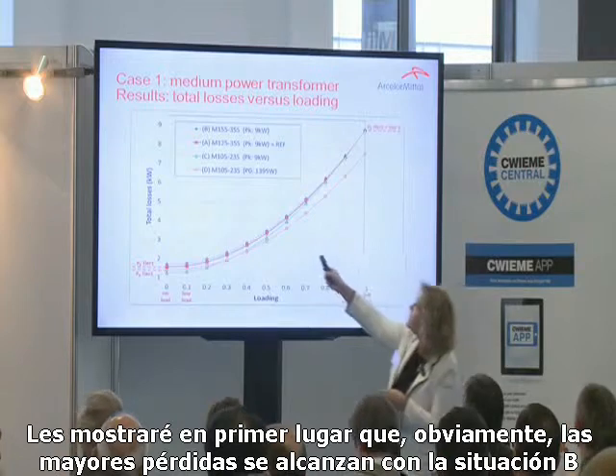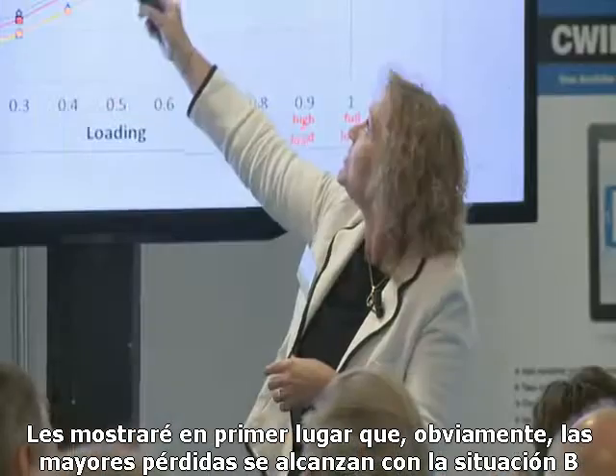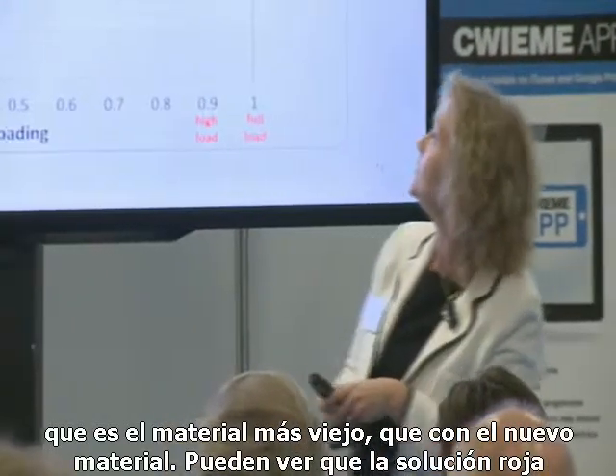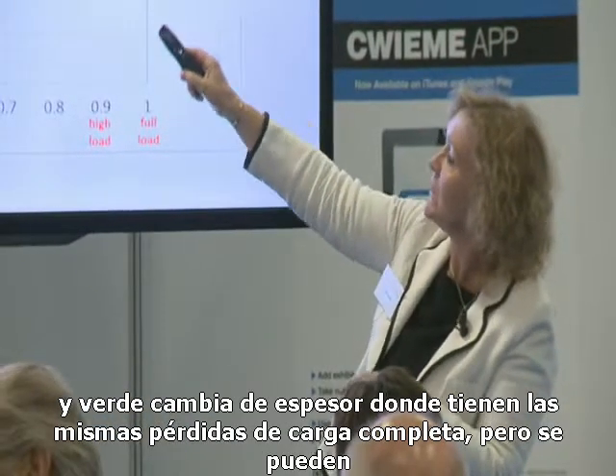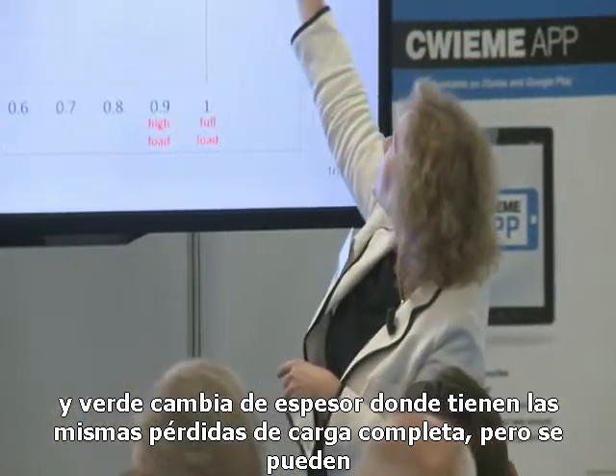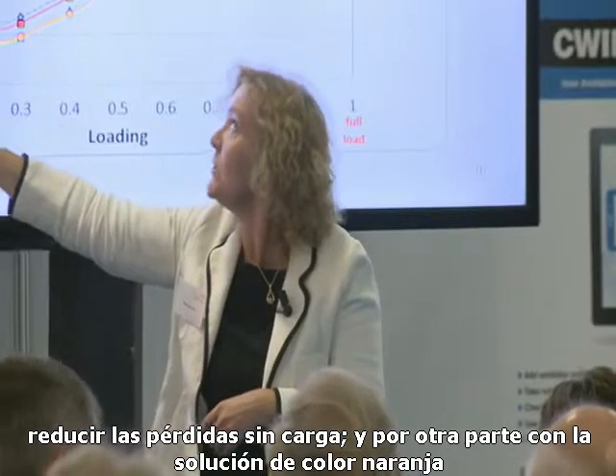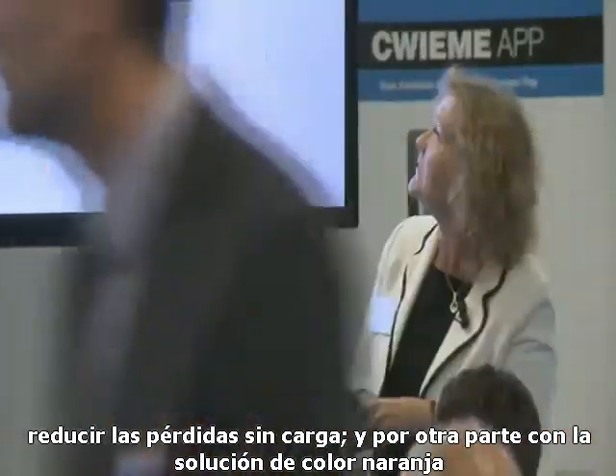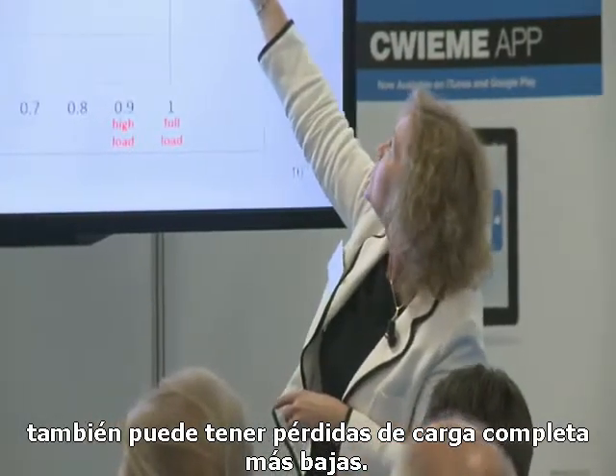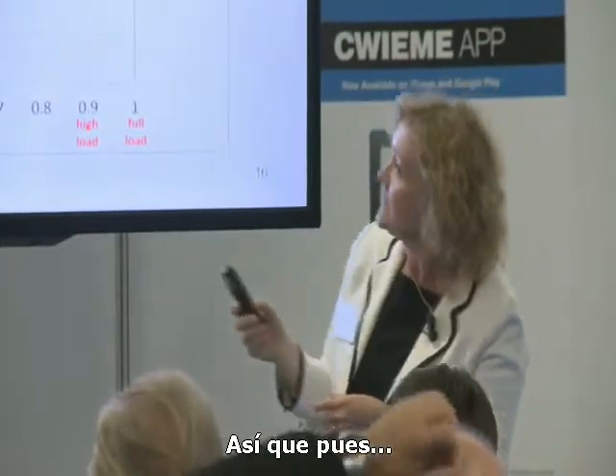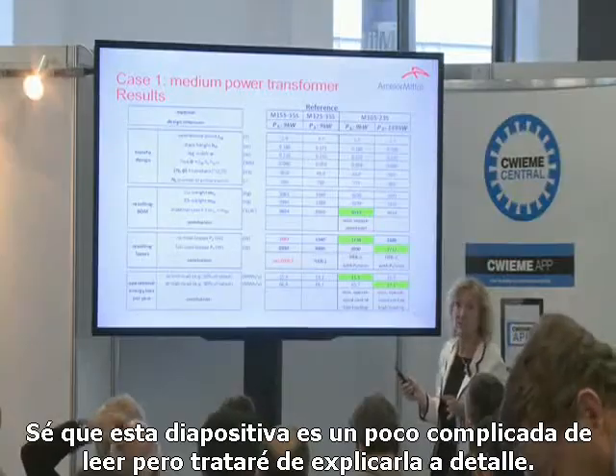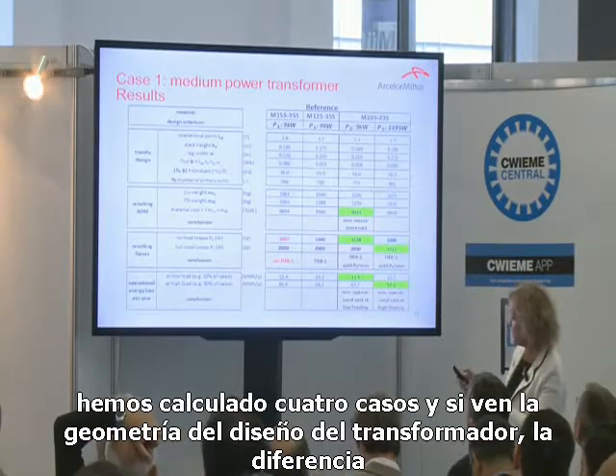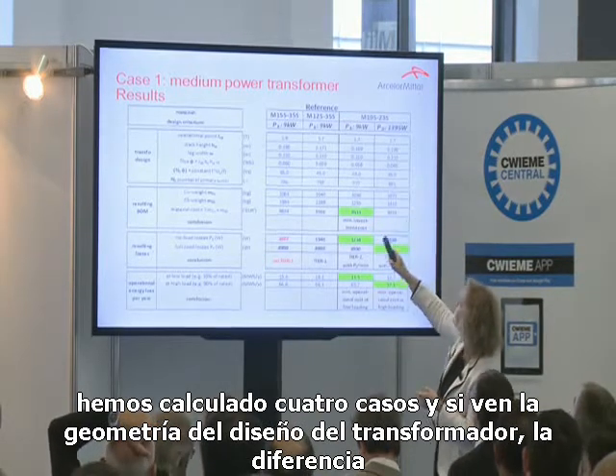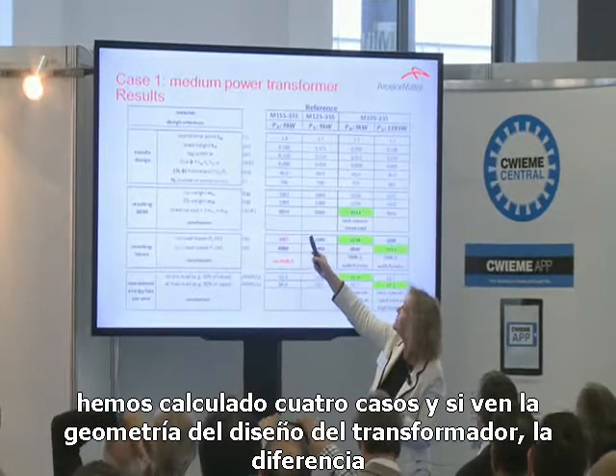I will show you first of all that obviously the highest losses are reached with situation B, which is the old material. Then with the new materials, you can see the red and the green solution, changing the thickness, where you have the same full load losses, but you can reduce the no load losses. And on the other hand, with the orange solution, you can have even also lower full load losses. So the best, although this table is a bit heavy to read, but I'll try to explain it a little bit further.